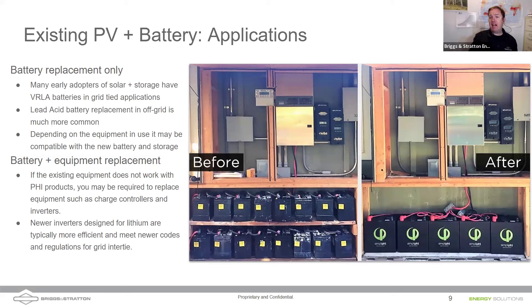The Outback Radian and Outback charge controllers in the example are relatively newer equipment, so we can program the set points — float, bulk, low battery cutout voltage — to treat our lithium-ion batteries the way they want to be treated. If you have older pieces of equipment, you may need to think about replacing the balance of system as well. Some of this newer equipment can even be a grid-interactive system if you're grid-tied.